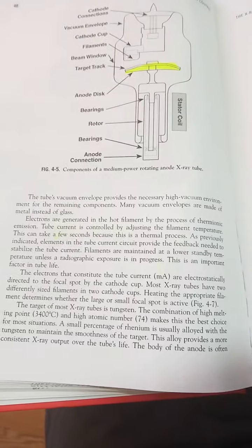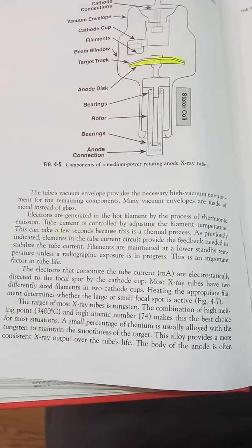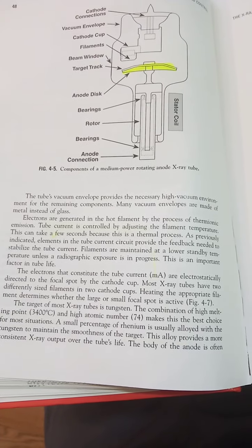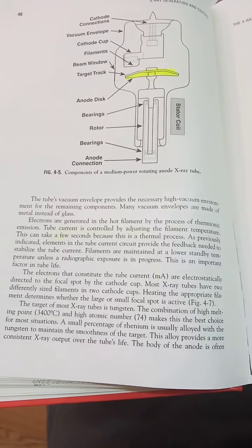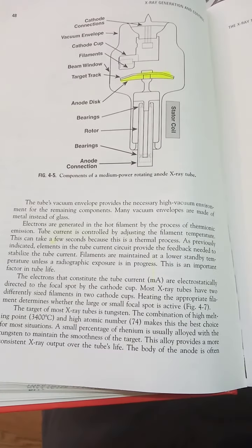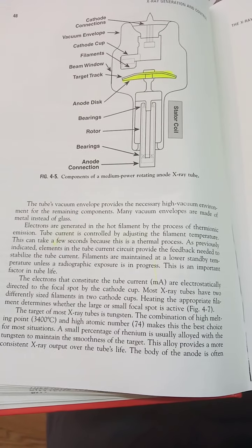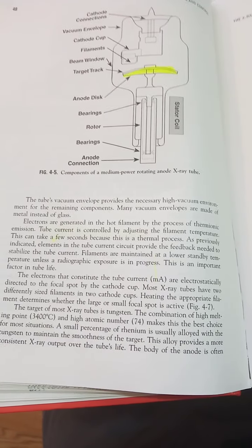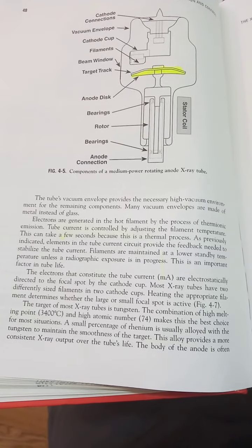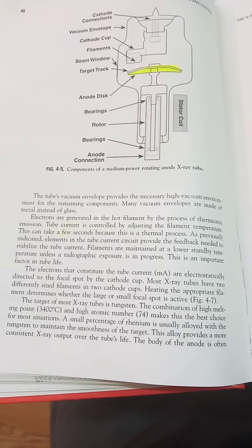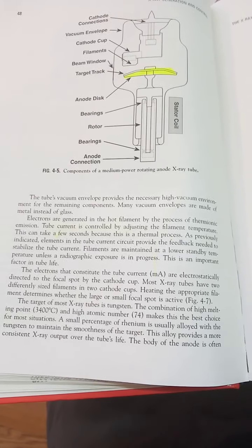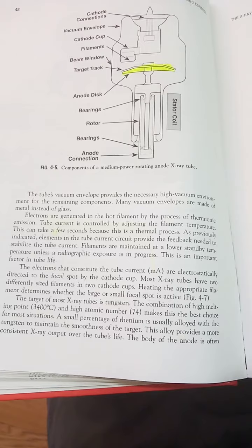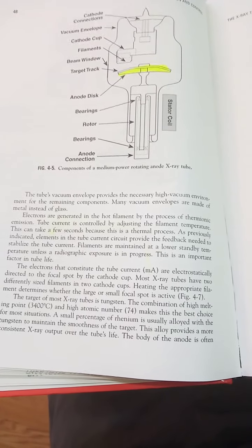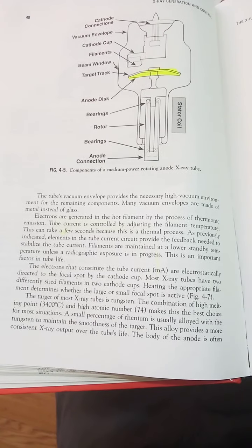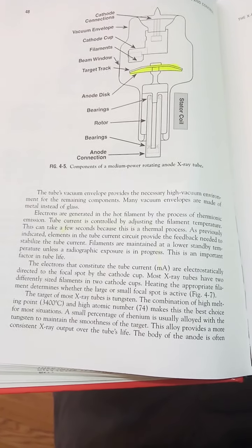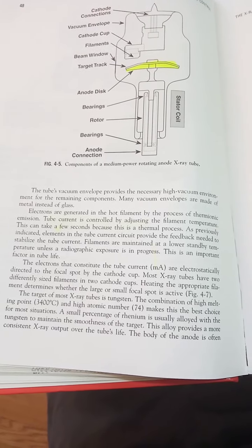So the electrons that constitute the tube current in milliamps are electrostatically directed to the focal spot by the cathode cup. Most X-ray tubes have two differently sized filaments in two cathode cups. Heating the appropriate filament determines whether the large or small focal spot is active. The target of most X-ray tubes is tungsten. The combination of a high melting point, 3400 degrees, and high atomic number, 74, makes tungsten the best choice for most situations. A small percentage of rhenium is usually alloyed with tungsten to maintain smoothness of the target. This alloy provides a more consistent X-ray output over the tube's life.